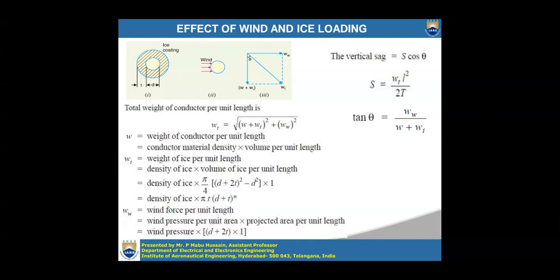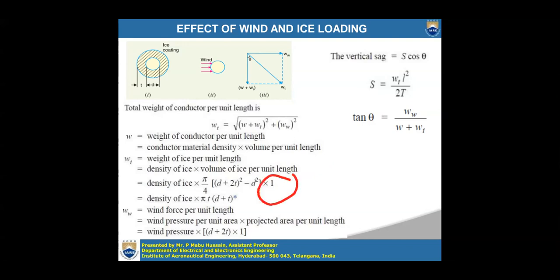If conductor material density and volume per unit length are given, then W = density × volume per unit length. Similarly, the weight of ice per unit length may not be given directly. They may give the density of ice and the volume of ice per unit length, or they may give the diameter of the conductor and thickness of the ice. Depending on what values are given, you use either formula. When diameter d and ice thickness t are given, Wi = density of ice × (π/4) × [(d + 2t)² − d²] × 1.